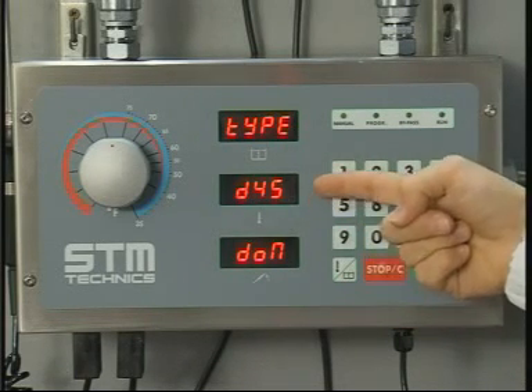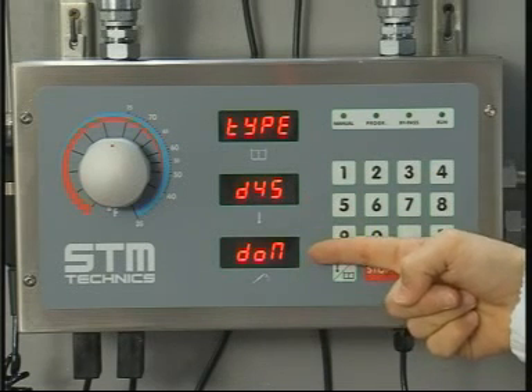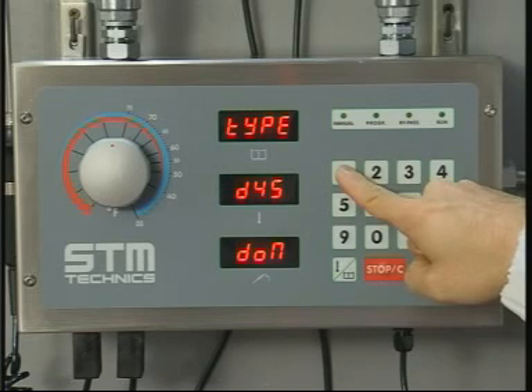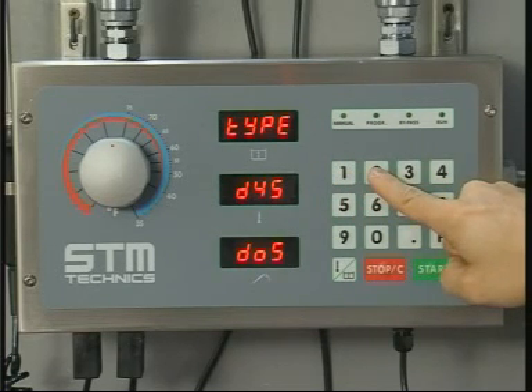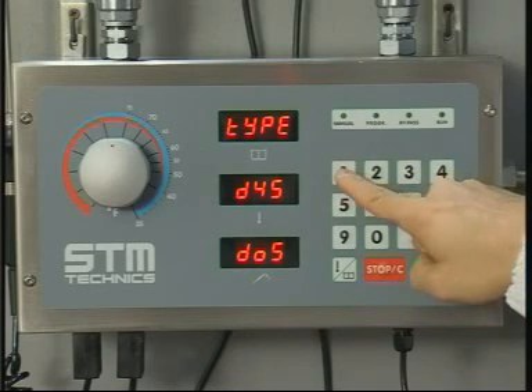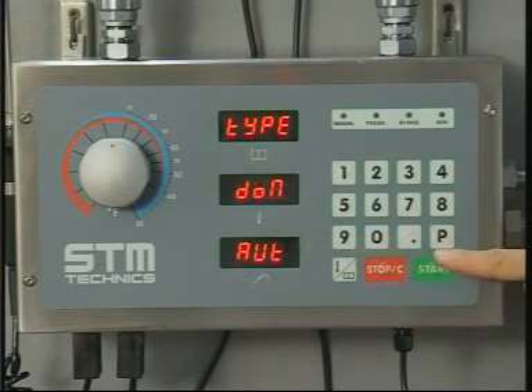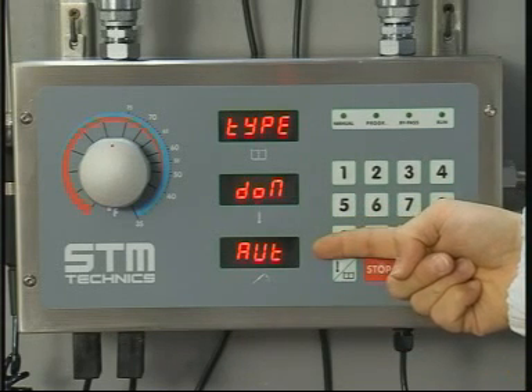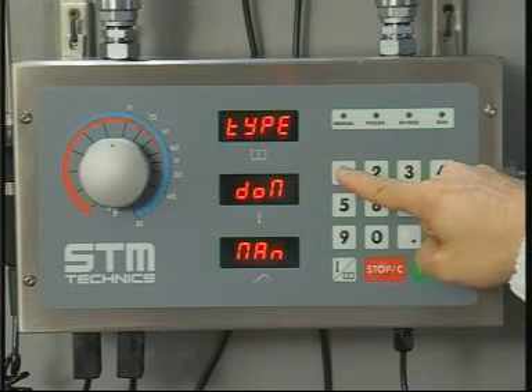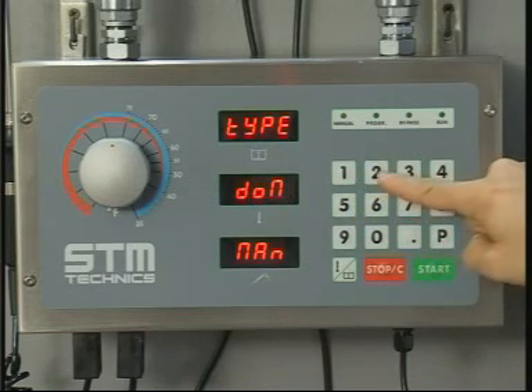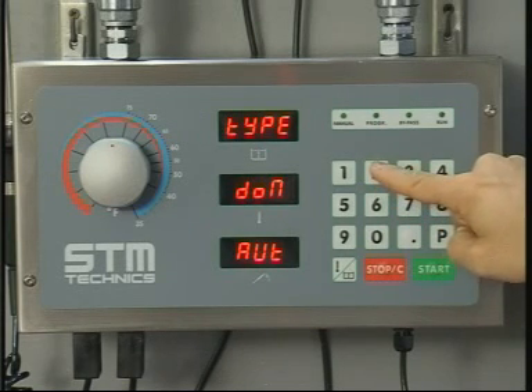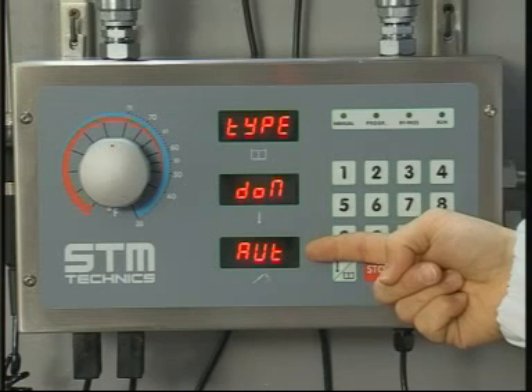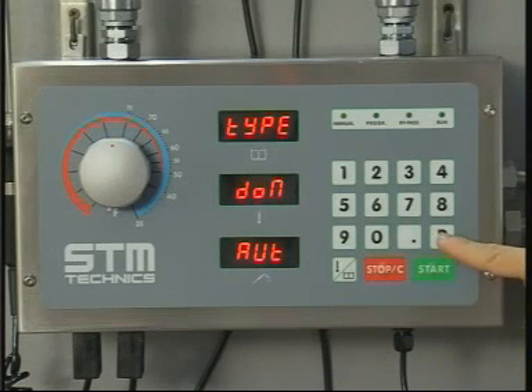Type D45 DOM. This display defines the type of machine. DOM means doser mixer, and DOS is only doser. Default DOM. Type DOM MAN or AUT. This display is for setting the electronics for Domix 45 man or Domix 45 AUT, with reference to the type of bypass. Manual valve for the first option, selected by pushing 1. Automatic valve for the second one, selected by pressing 2.